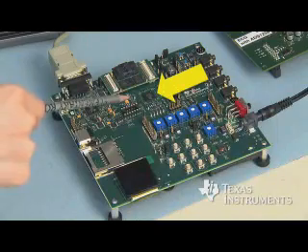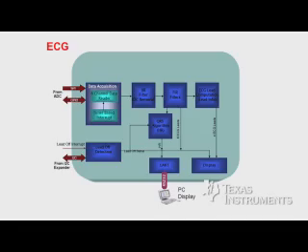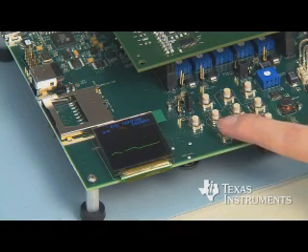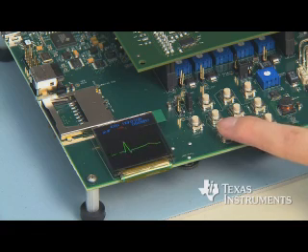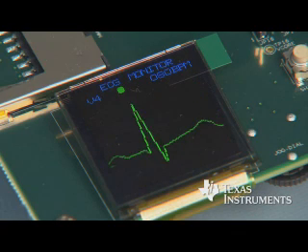The DSP subsystem performs digital signal processing on the ECG signals, including filtering, remaining leads computation, and QRS detection for heart rate computation. The DSP subsystem is also responsible for managing user inputs and the display control of the results. The ECG results are displayed on the OLED display that is included on the DSP board.